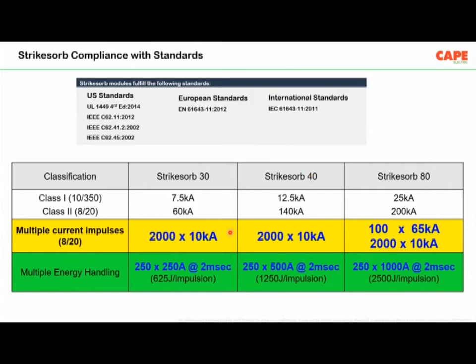These busbar mounted SPDs are tested for multiple strikes. Say, for example, 2000 strikes of 10 kiloampere, 100 strikes of 65 kiloampere. So for critical electrical installations, you need these kinds of high quality SPDs.